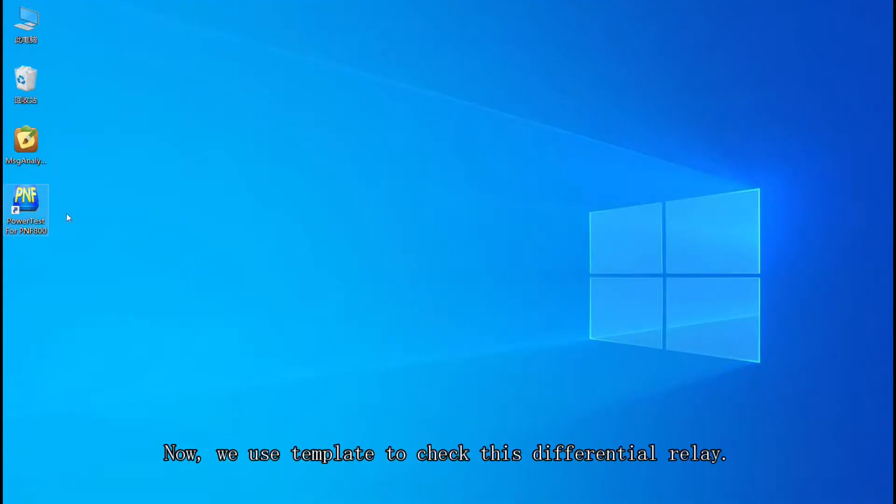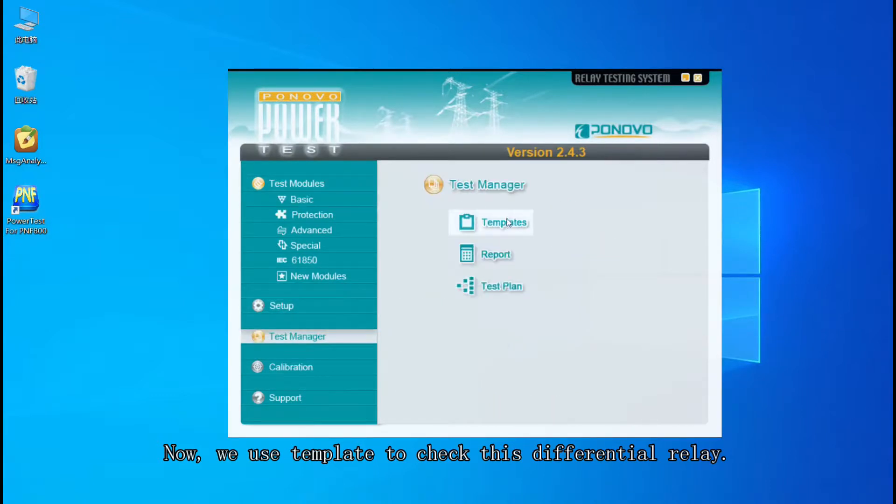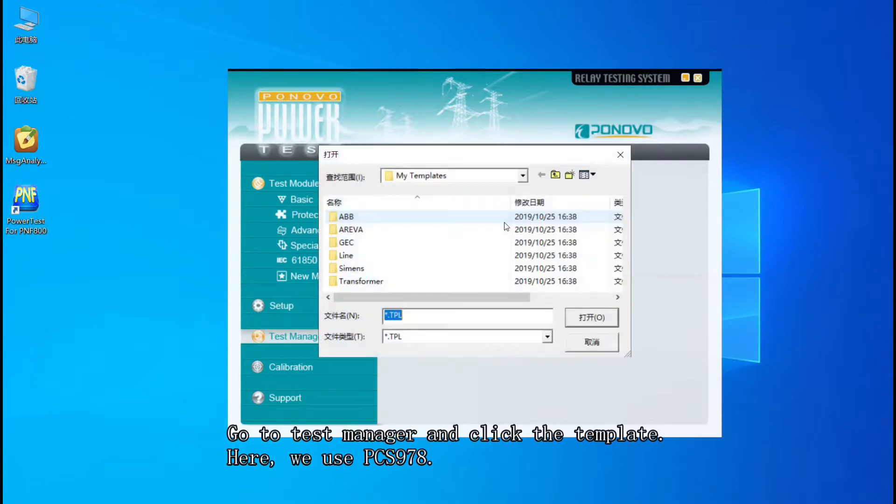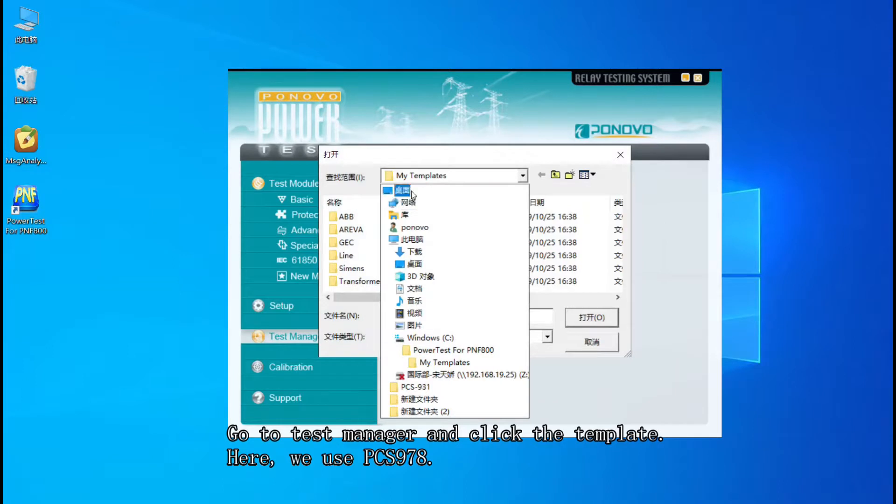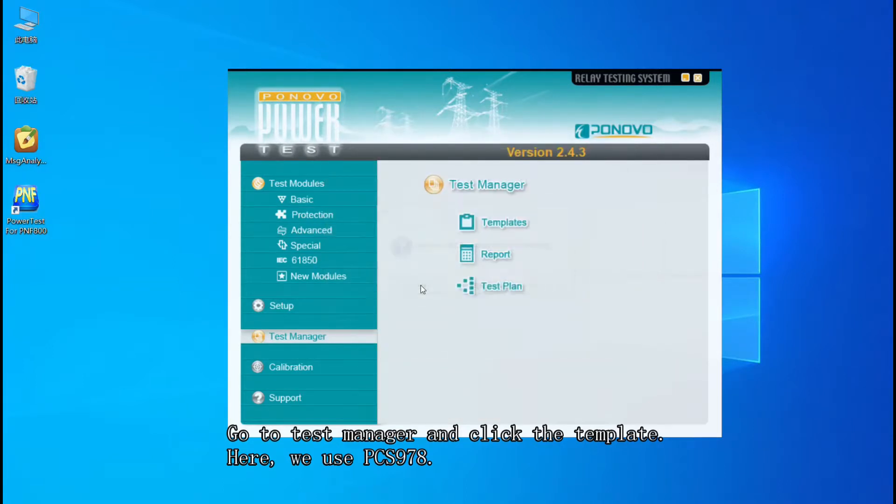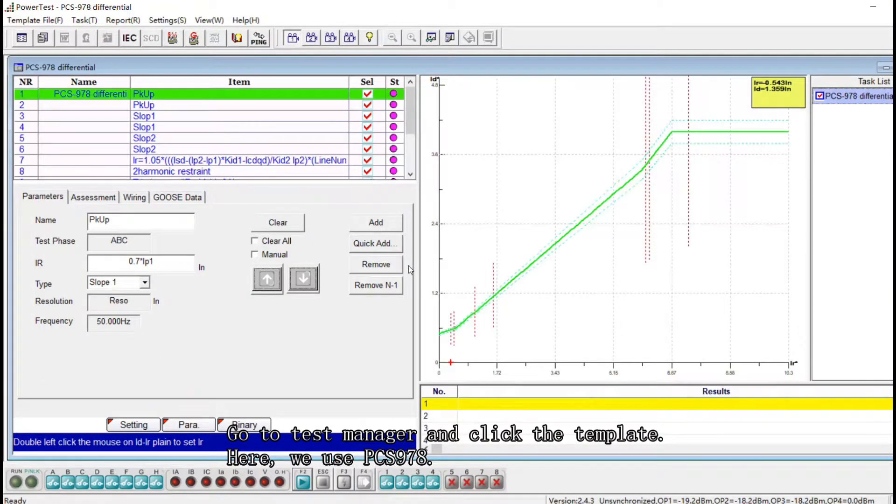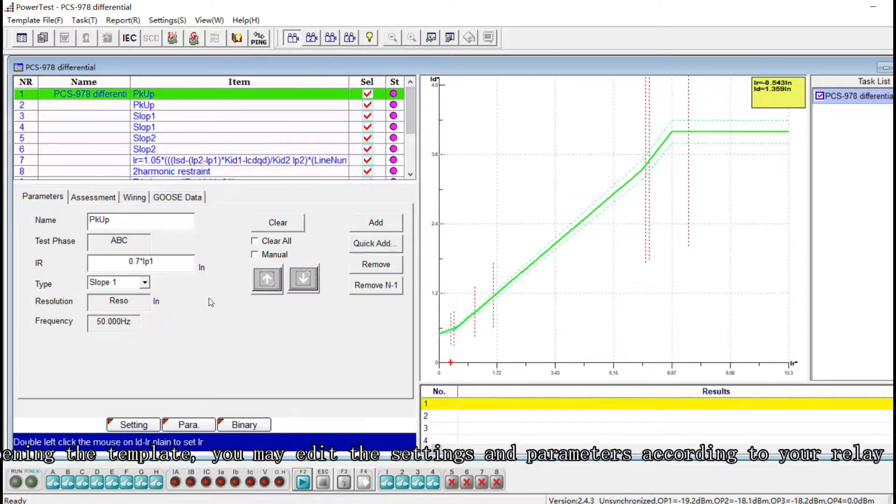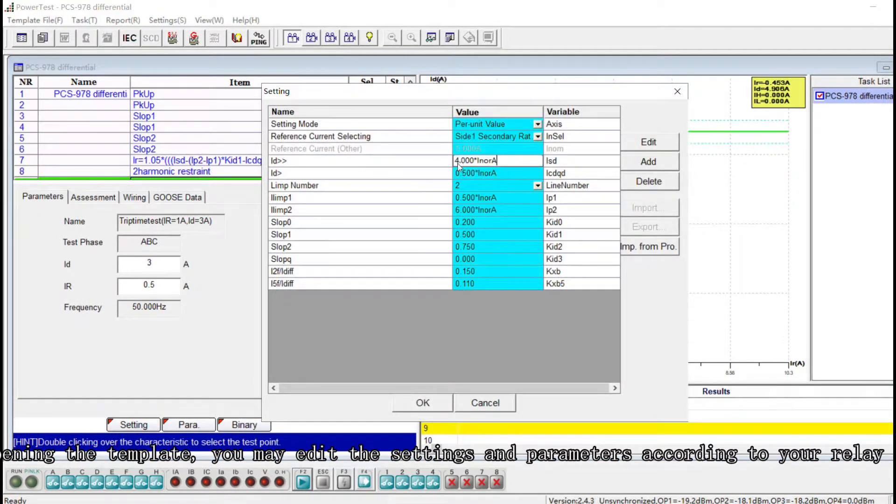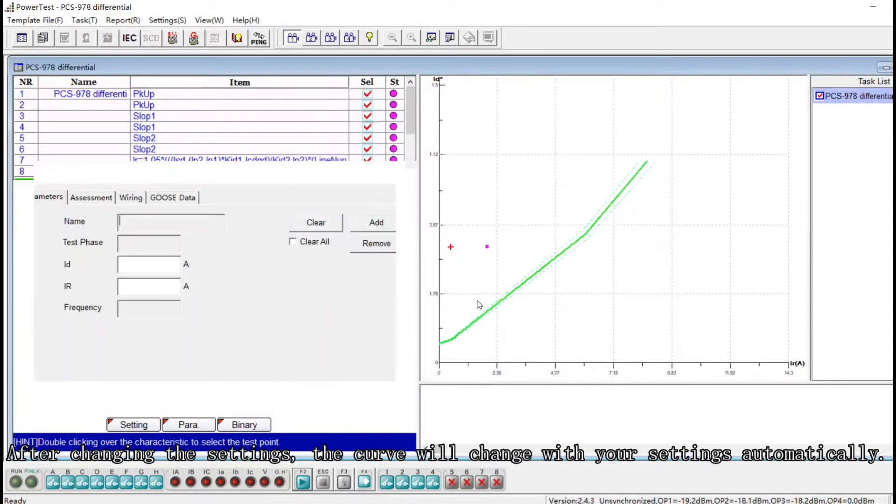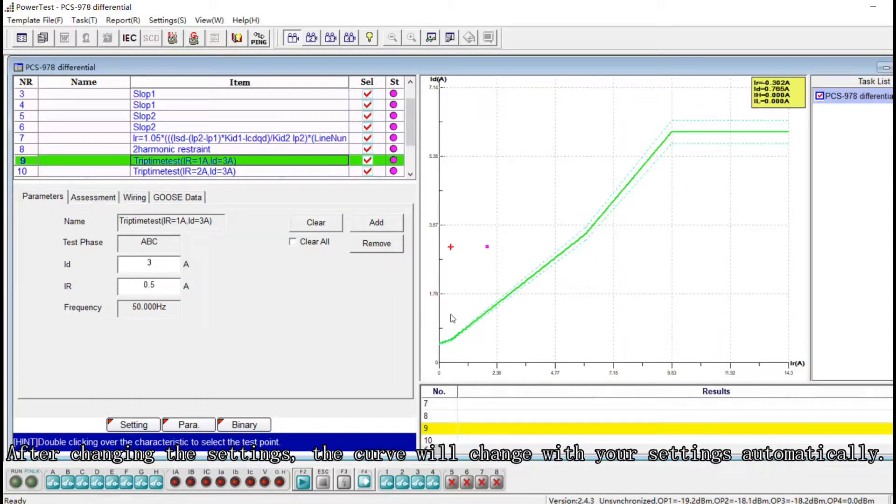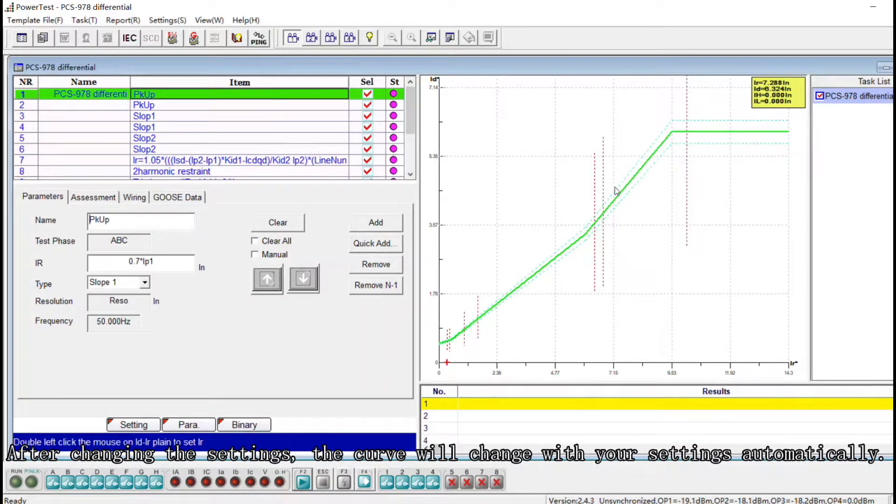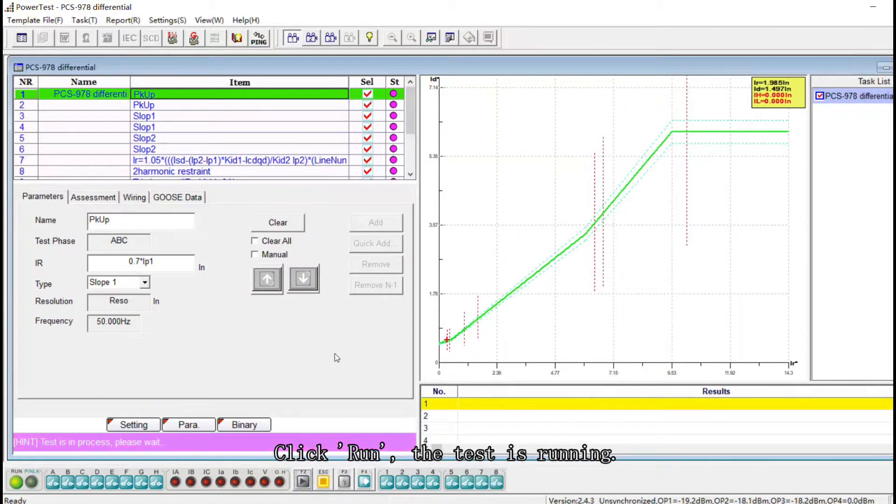Now we use template to check this differential relay. Go to Test Manager and click the template. Here we use PCS 978, open the template. You may edit the settings and parameters according to your relay. After changing the settings the curve will be changed with your system settings automatically. Click run, the test is running.